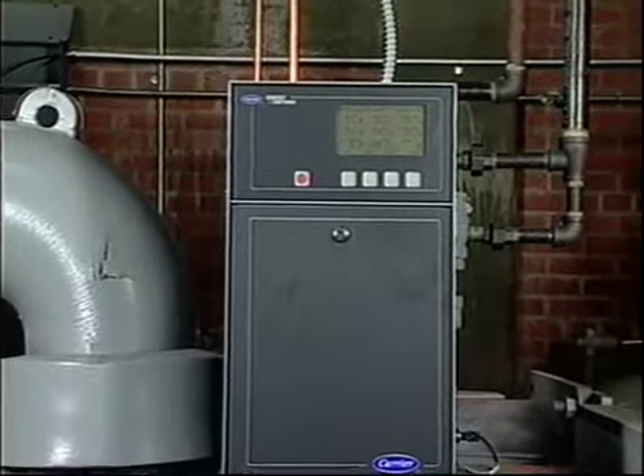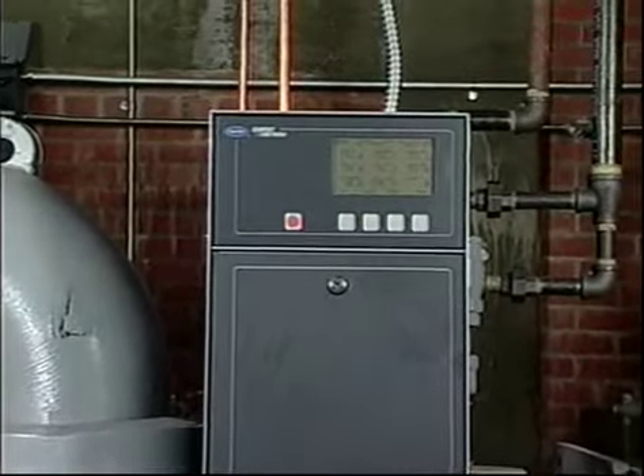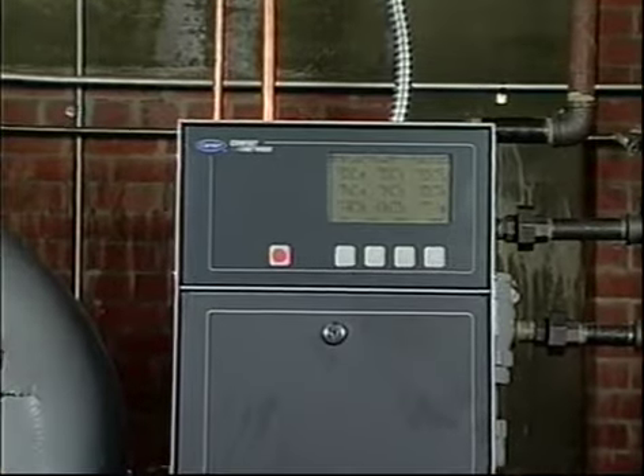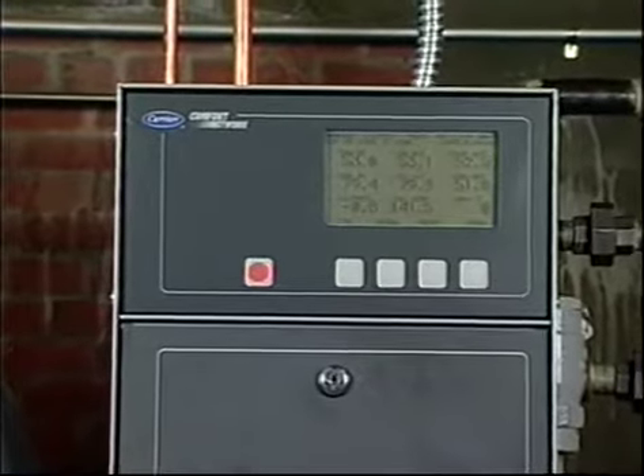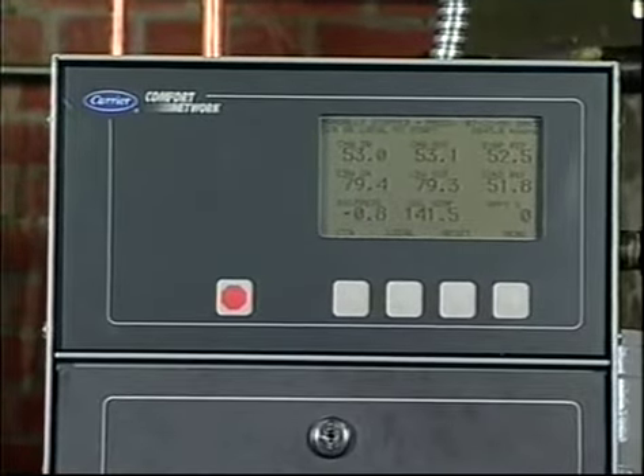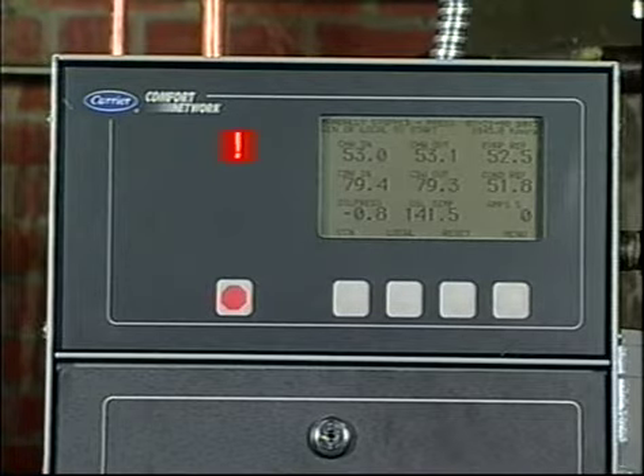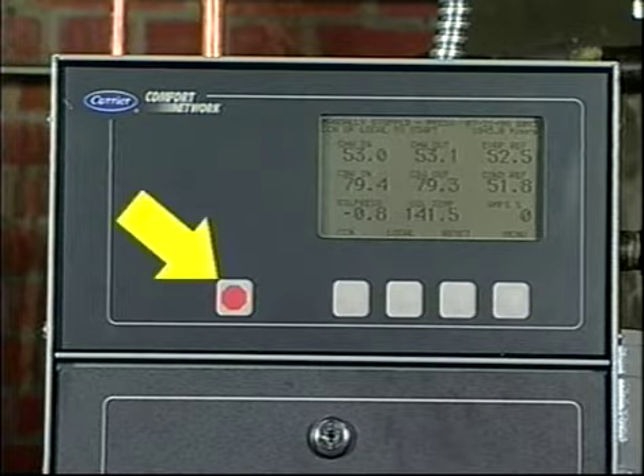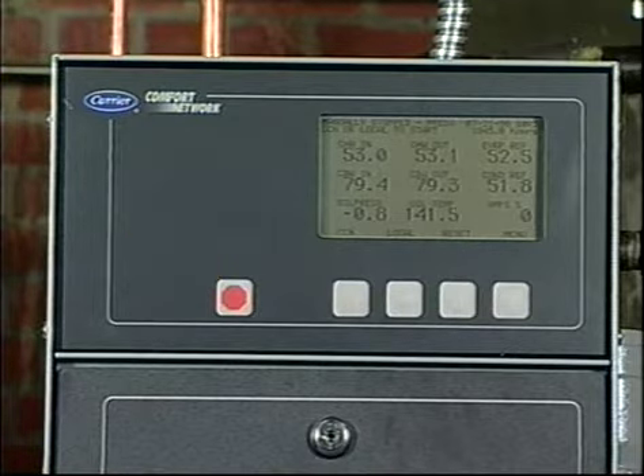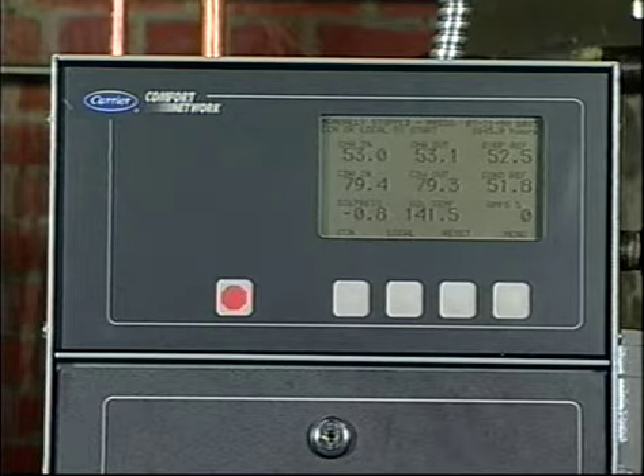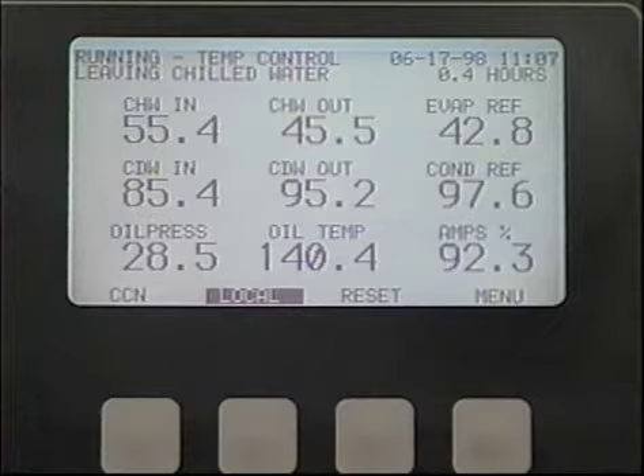Now let's take a closer look at the controls. The LID is the device that lets you communicate with the controls. It contains a liquid crystal display and 4 keys used for starting the chiller and accessing the control software. To the left of the display is the alarm light, which flashes when abnormal conditions occur. Below the alarm light is the stop button, which, if depressed for at least 1 second, will cause the chiller to shut down. Unless another screen has been manually called up, the LID continuously displays a default screen containing a lot of useful information. Things like date, time, operating or shutdown mode, status messages, alarm messages, and 9 of the most important operating temperatures and pressures.